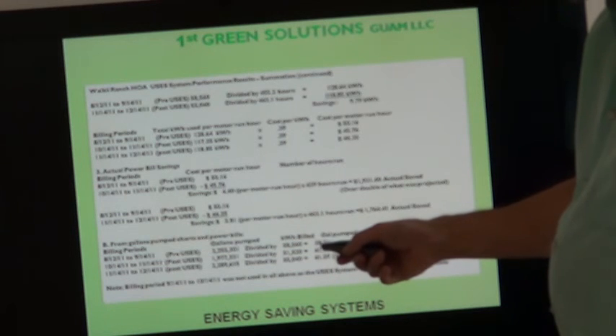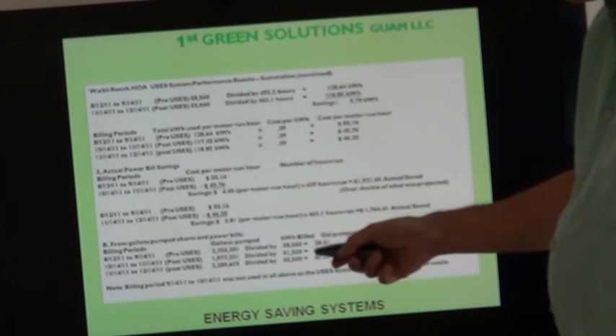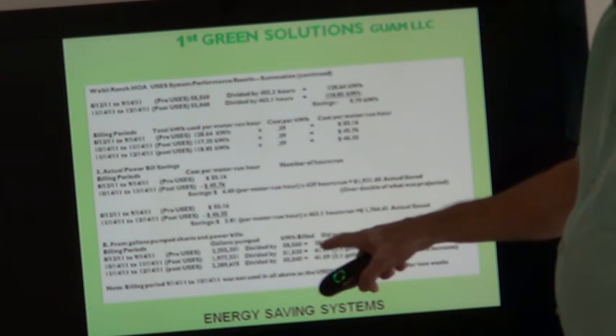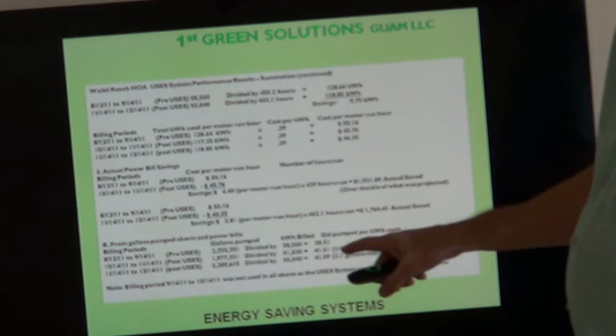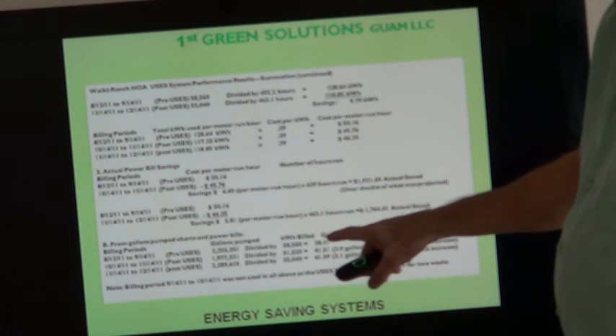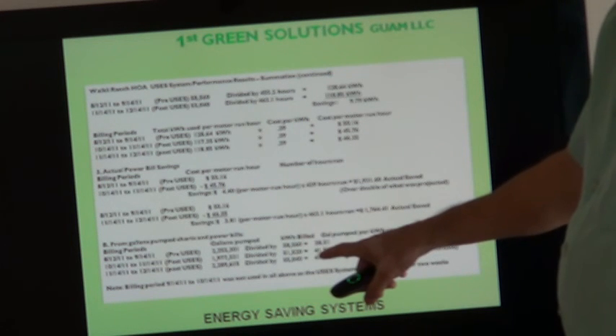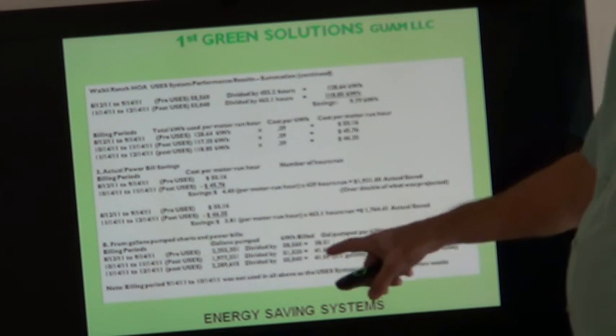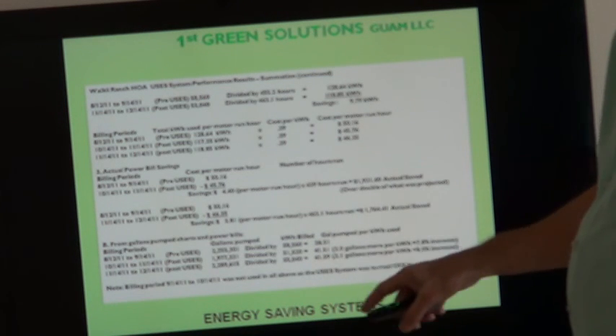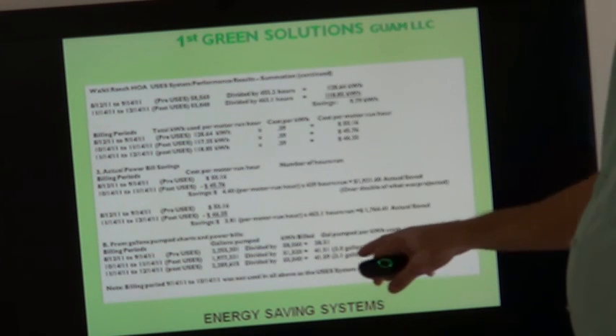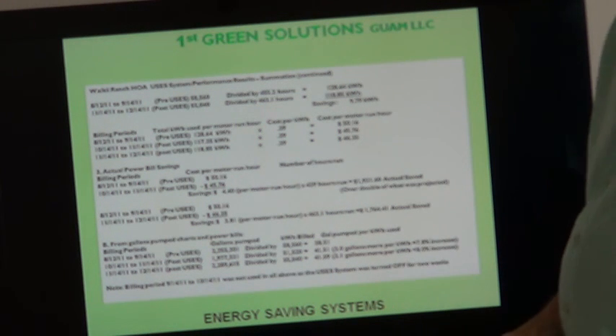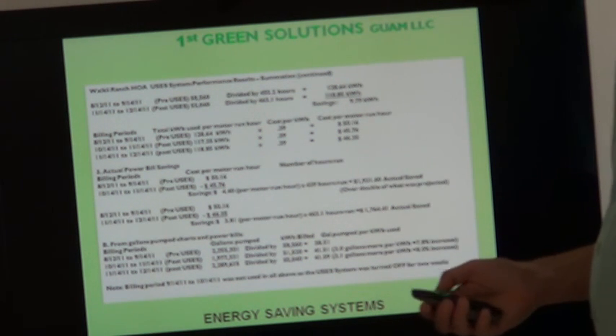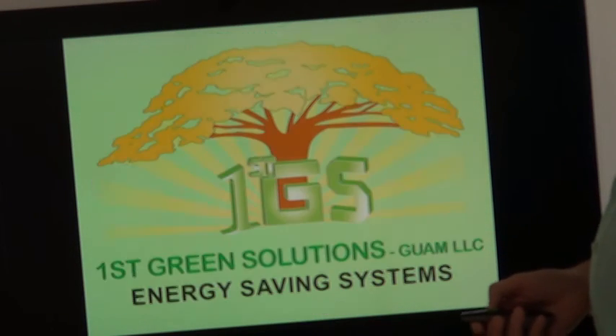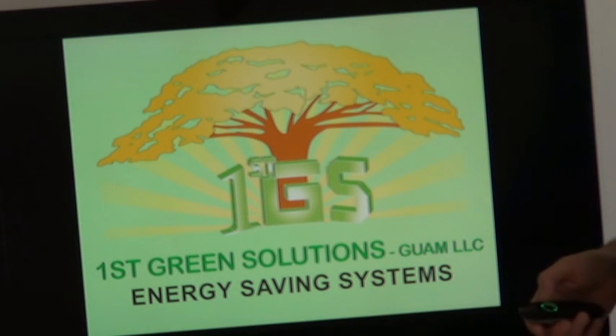This resulted in the amount of kilowatt hours being reduced for the amount of gallons pumped. So in this case, they were pumping 38.5 gallons for every kilowatt they were using, and we were able to increase that to 41.5 and 41.59 gallons for every kilowatt that was being used, and that represents an 8% increase in performance in the pumps. And that's our PowerPoint presentation.